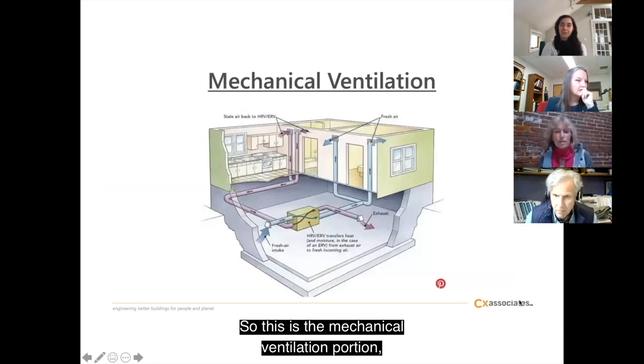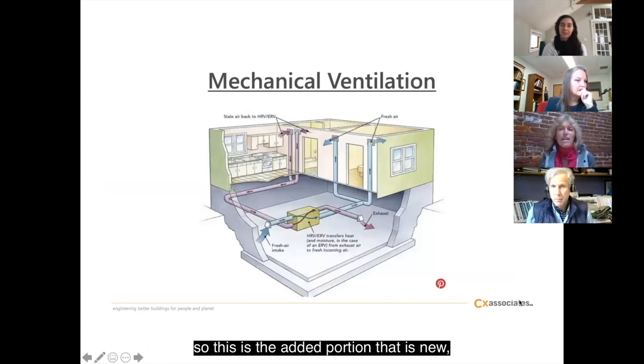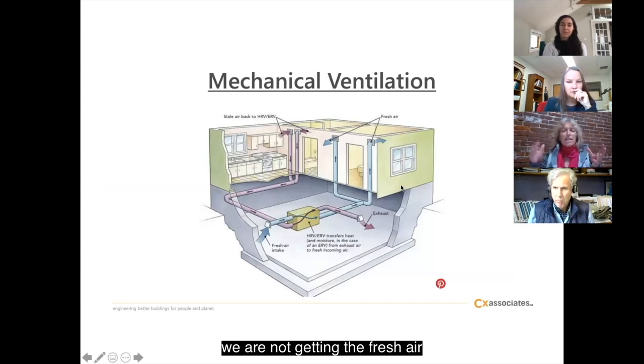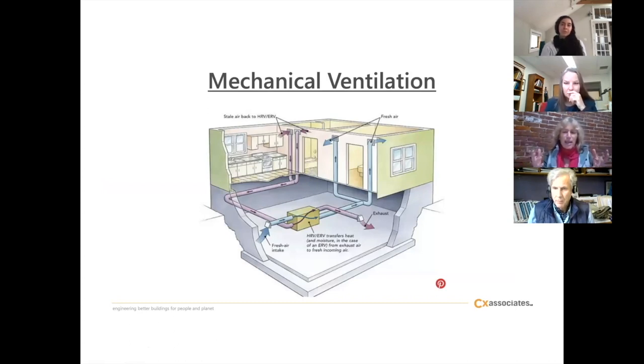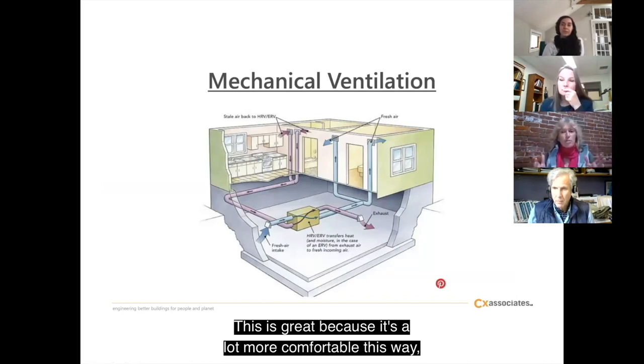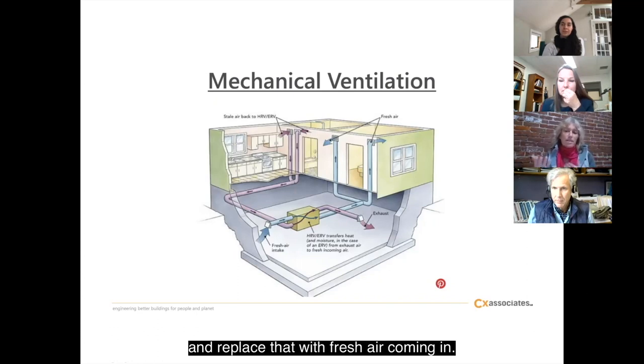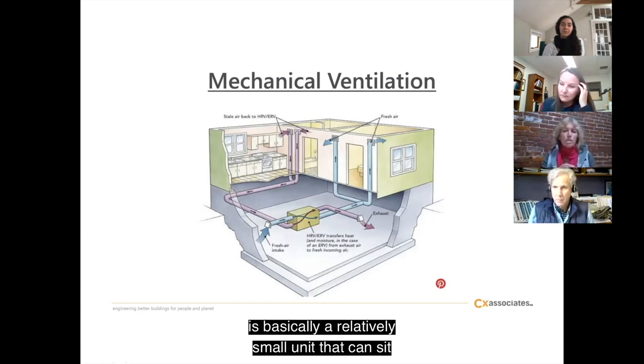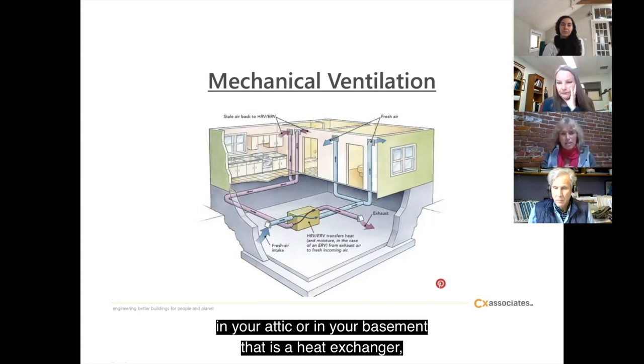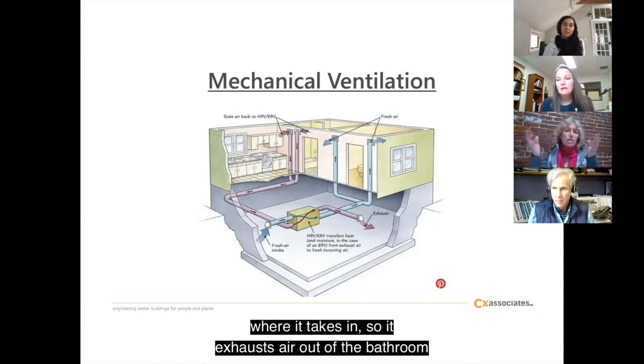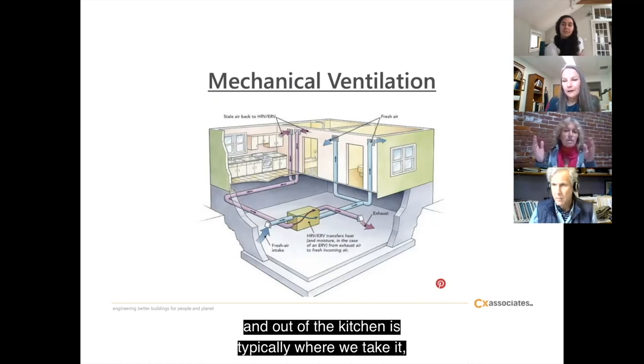So this is the mechanical ventilation portion. This is the added portion that is a new component to the mechanical system. If we have tightened up our building, we are not getting the fresh air that used to come in through leaks. This is great because it's a lot more comfortable this way, but we need to make sure that we take the moisture, odors and stale air out of the building and replace that with fresh air coming in. Mechanical ventilation is basically a relatively small unit that can sit in your attic or basement that is a heat exchanger, with quite small ductwork that can go into the walls and is run through the house, where it exhausts air out of the bathroom and the kitchen, which is typically where we take it.